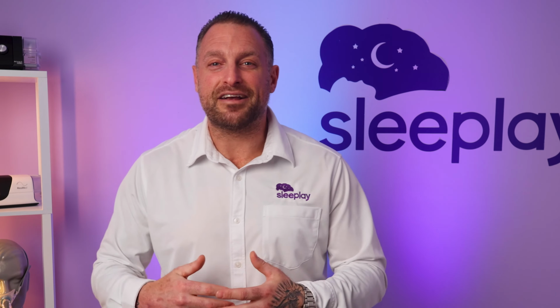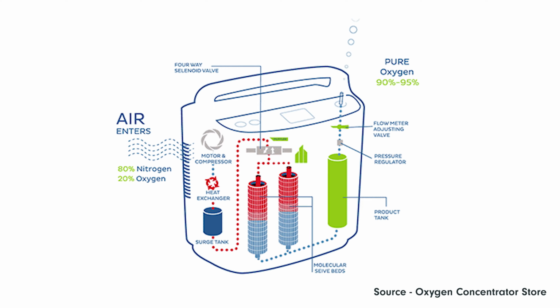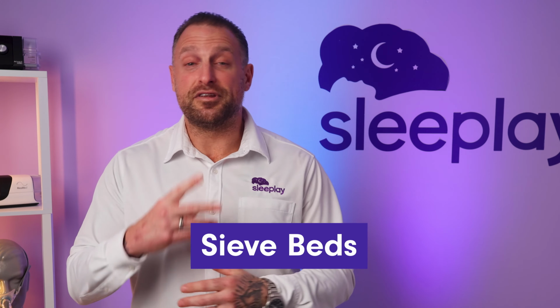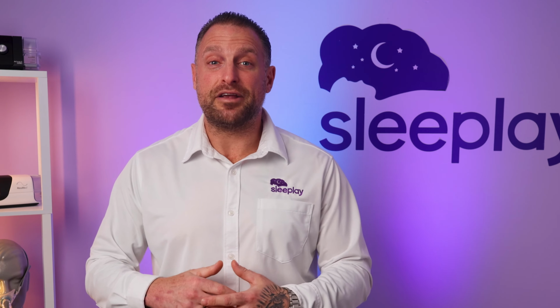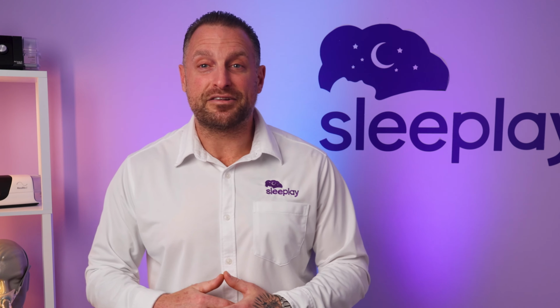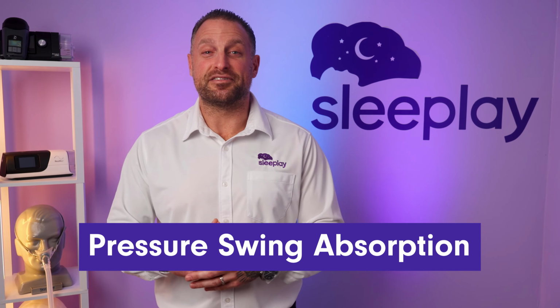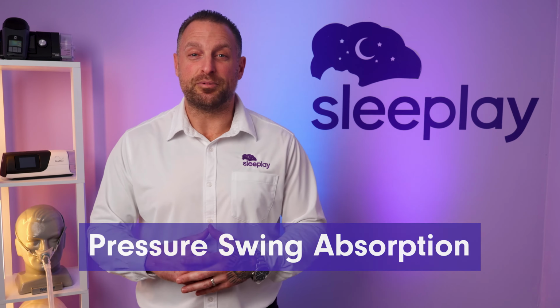To start off, an oxygen concentrator takes the air in the room and extracts the oxygen from it. It then filters the oxygen using special filters called sieve beds. There are usually two. These filters capture the nitrogen and allow purified oxygen to pass through into your nasal cannulas. This process is called pressure swing adsorption.